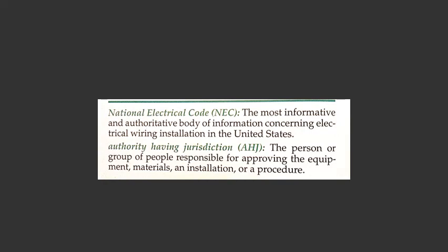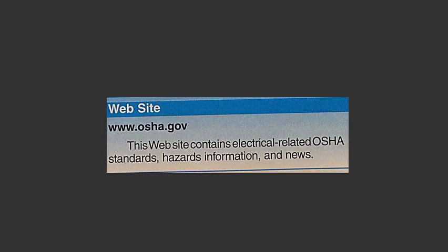Equipment and testing agencies. There are many recognized testing agencies throughout the U.S. and Canada. Each of these agencies is known as a nationally recognized testing laboratory, or NRTL, which tests materials and equipment submitted to them by electrical manufacturers. If the materials and equipment submitted measure up to the testing agency's expectations, the items are listed as suitable for electrical installation. In addition, the product will be labeled with a recognized mark to identify the testing agency that approved the product.